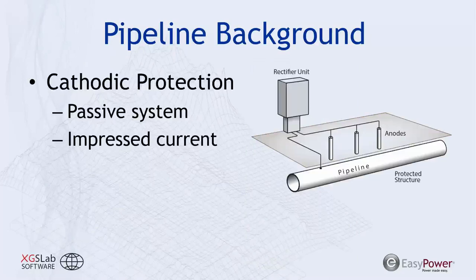Other things that are important to note about pipelines is that they may have cathodic protection on them, and that cathodic protection could be a passive system, or it could be an energized or an impressed current system. On the illustration on the right, we have a rectifier that is energizing the pipeline, and this allows for a cathodic protection that is tunable and can be monitored. But it's also another spot from an AC interference perspective that personnel are interfacing with that pipeline and could be a new potential hazard.